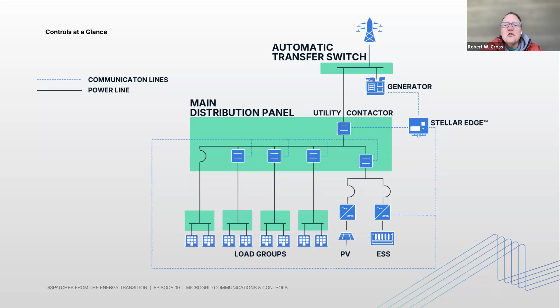And then the other trade-off we have to consider is, we've been talking about resilience and what the microgrid can do when off-grid, but what about when it's on-grid? How you're actually using it has a direct relationship to how much battery you have in reserve if an outage happens at the exact wrong time. So do you prioritize short-term resilience, where you want to be able to get through 2 hours anytime? That means you have a certain amount of reserve capacity not available for economics, so your returns are somewhat less.